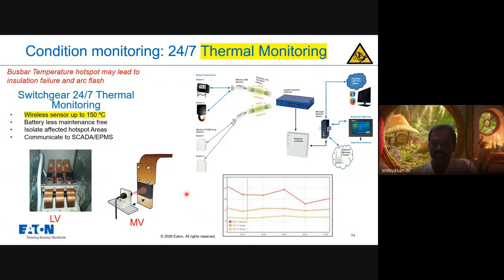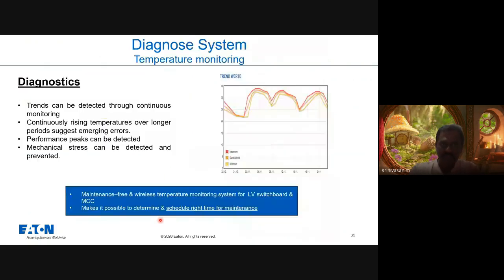Also, as I said earlier, at the BMS or SCADA level, we can see the real-time continuous values of the temperature. We can also see the average values and the minimum values. We have the solution for low voltage and also for medium voltage. As I said earlier, by having this diagnosis system, we can have a clear idea about the level of temperature and thermal condition inside the switchboard, so that we can take preventive actions well in advance to avoid any thermal issues happening in a bigger way.